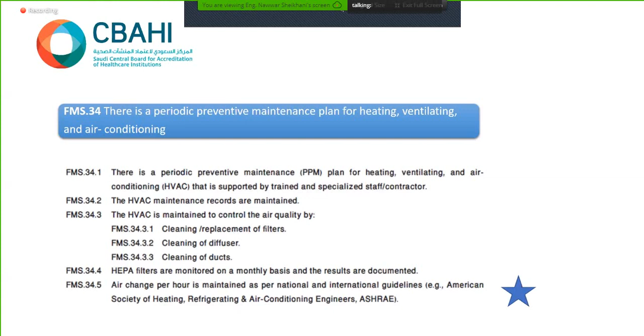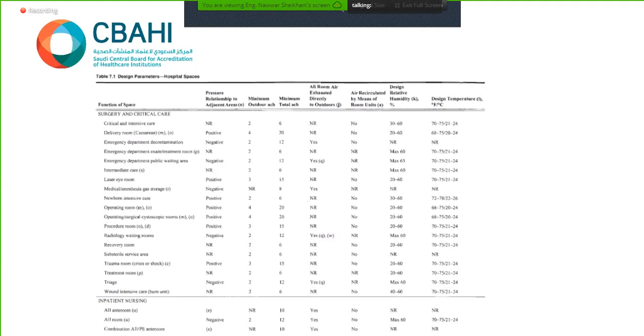Air change per hour. Actually, our reference here is the facility guidelines. They have a chapter retrieved from ASHRAE talking about air change per hour, like this. Here, for instance, critical and intensive care, let's take the operation room, it should be positive pressure. We should have 20 air changes per hour, not 100% fresh air, only 20% fresh air. Okay, how to calculate it? In this sample, we get the return measured in CFM, cubic feet per minute. We should mention the total volume in cubic feet of a certain room, then calculate the air change per hour. What is required, what is existing.